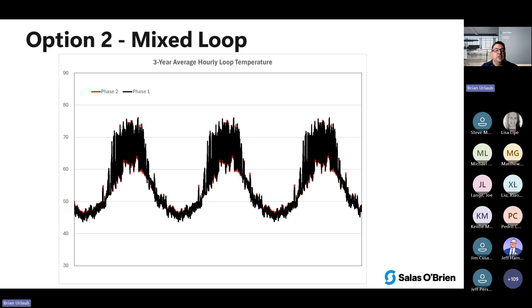We modeled the COP of these systems, and to highlight this about thermal energy networks as a whole: because of the mass of these systems and how they're designed, if you design a single family home or commercial building around a certain parameter, you generally hit that parameter, like 32 degrees for instance. You don't see that in these thermal energy networks because of the flywheel effect, the mass of the fluid, the volume it takes to change temperature, and of course the mass of the Earth we're connected to.